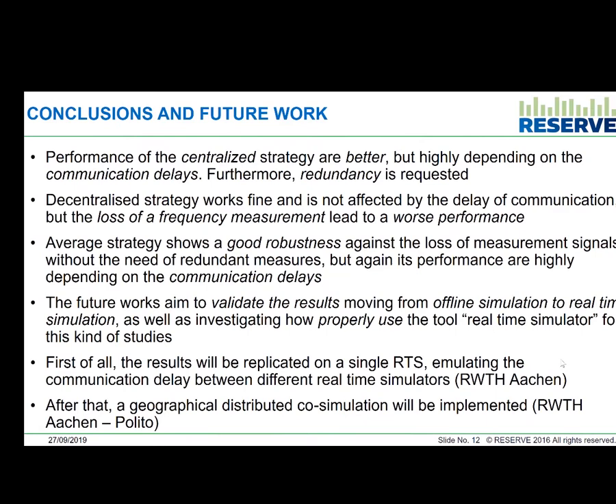The conclusions: this was a proof of concept investigating different communication delays and the loss of at least one measurement point. The centralized and average strategies can achieve good performance, but are strictly dependent on the communication delay — this is the main point to take into account when using only one source. The decentralized strategy is not affected by delay, since there is no delay from measurement to use, but the loss of a frequency measurement can lead to worse performance.